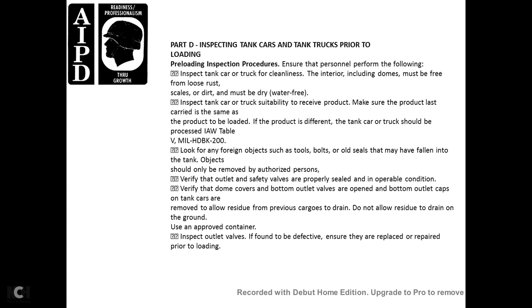Part D: Inspection of Tanker Cars and Tanker Trucks — Pre-loading Inspection. Personnel performing inspection must check: tanker truck cleanliness — tanks must be free of loose dirt, scale, and free water; ability to receive the product — verify the last product carried is the same as the product to be loaded. If a different product was previously carried, the tank should be cleaned per Military Handbook 200, Table 5-5.